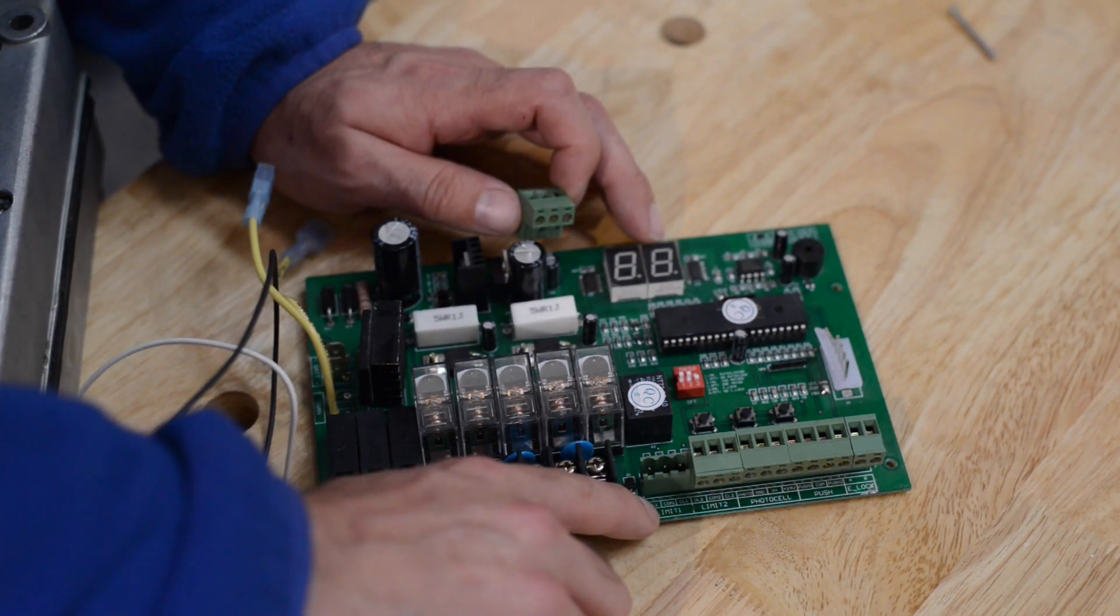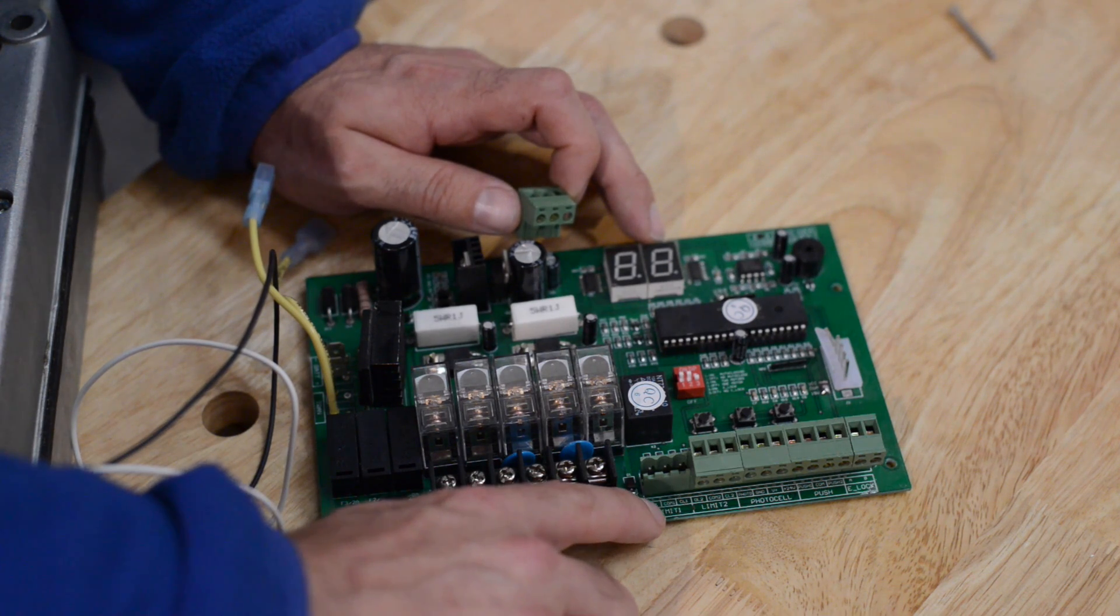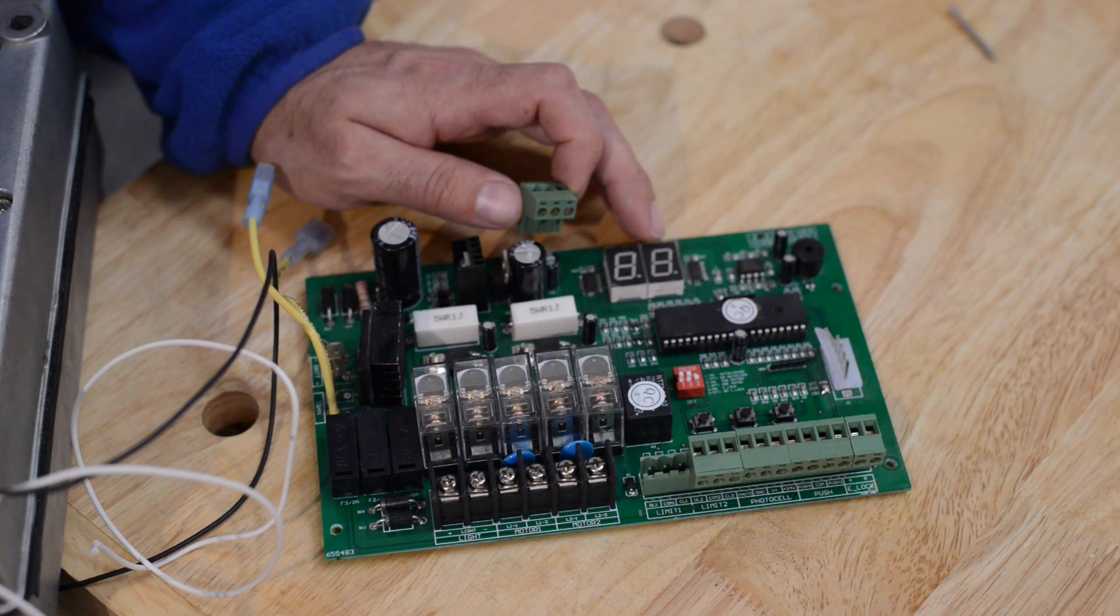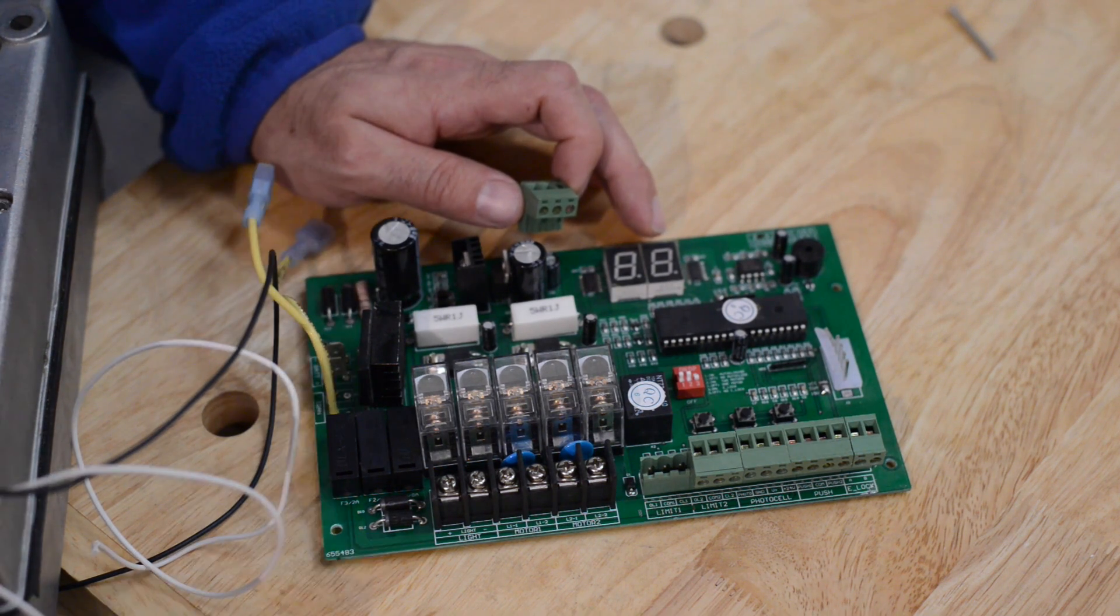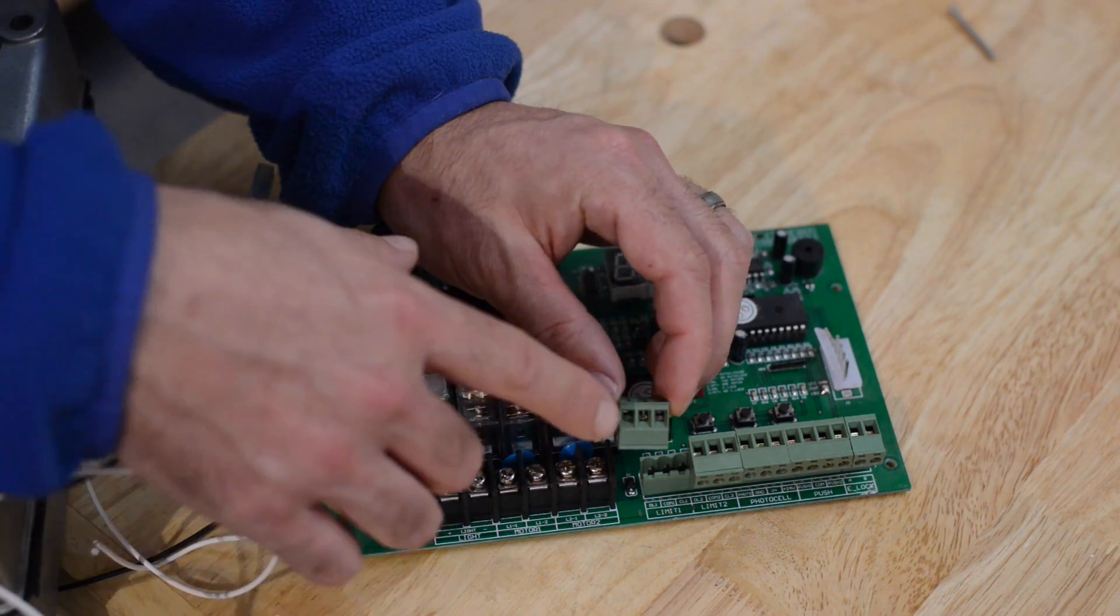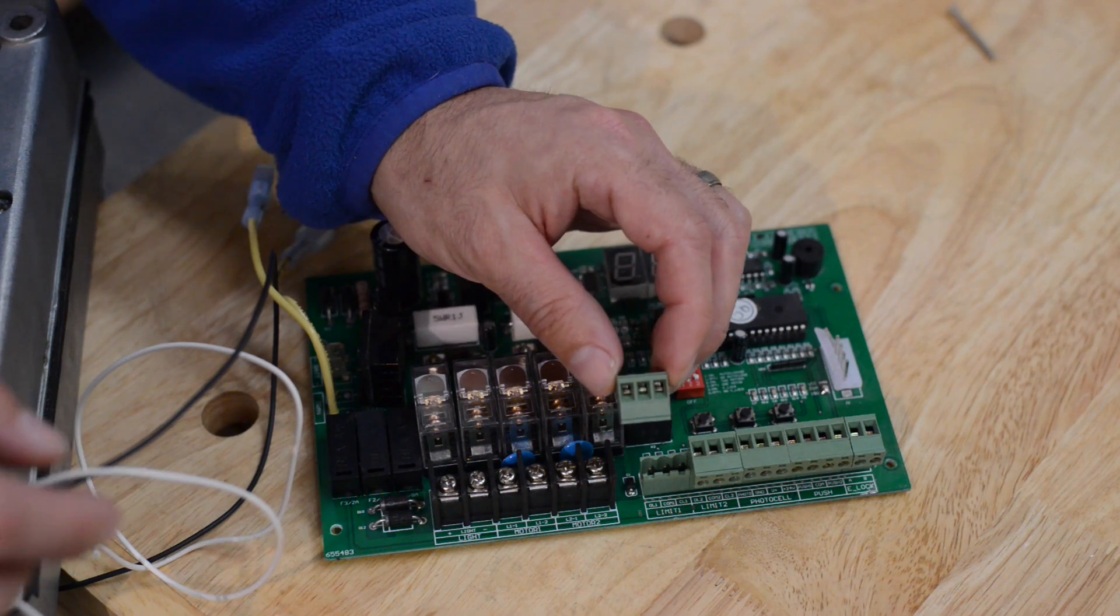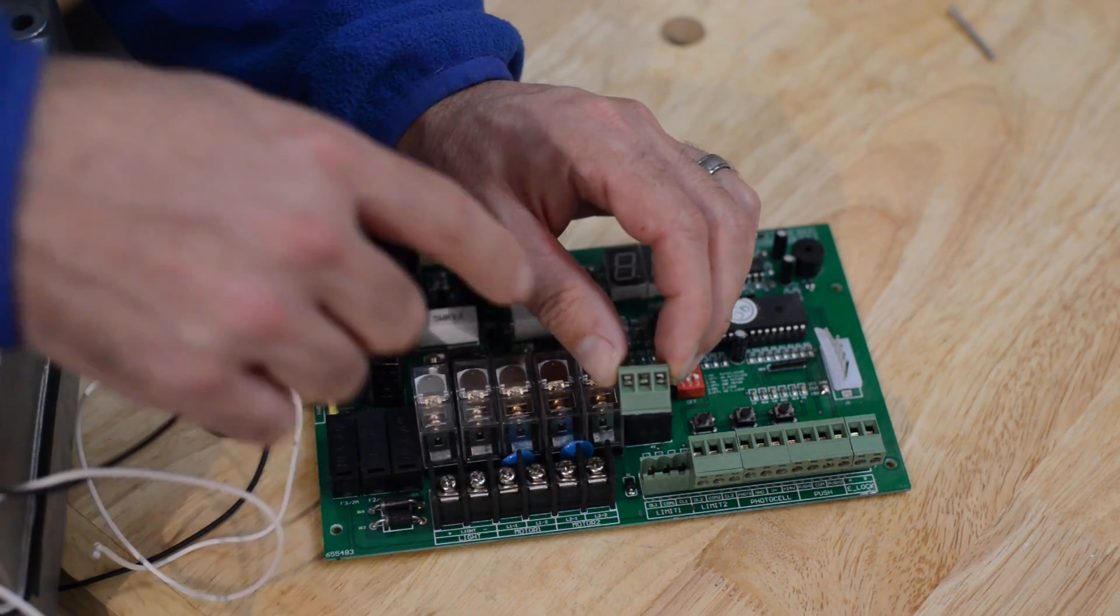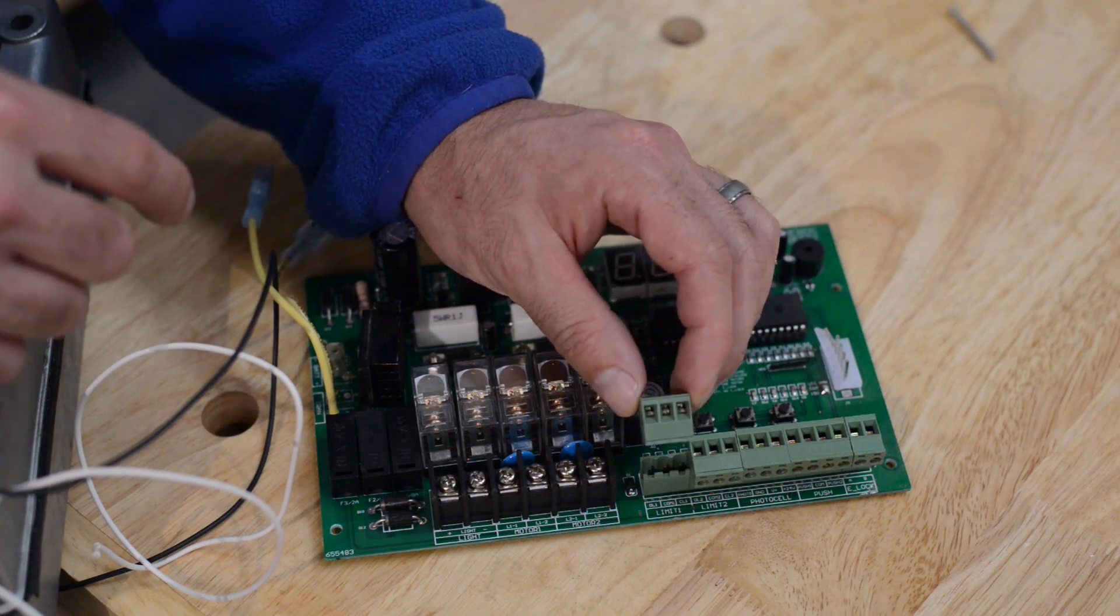Now in even smaller writing here you will see OL1, COM1 and CL1. COM1 is where your two commons from your limit switch are going to go to. So in your terminal block you are going to wire either the two wires from the COM or the two wires that were connected to a single wire leading back to this terminal. The center terminal on the block.